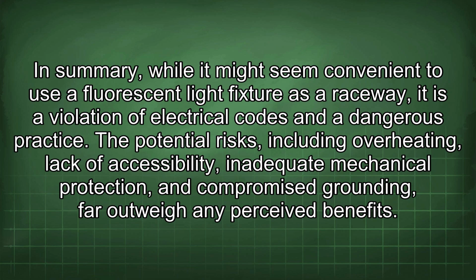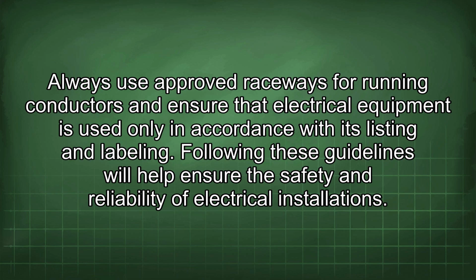In summary, while it might seem convenient to use a fluorescent light fixture as a raceway, it is a violation of electrical codes and a dangerous practice. The potential risks, including overheating, lack of accessibility, inadequate mechanical protection, and compromised grounding, far outweigh any perceived benefits. Always use approved raceways for running conductors and ensure that electrical equipment is used only in accordance with its listing and labeling. Following these guidelines will help ensure the safety and reliability of electrical installations.